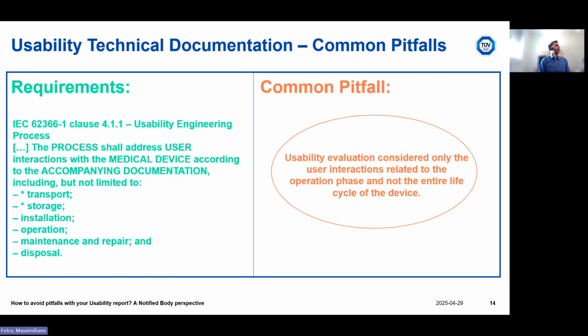Okay, let's start from clause 4.1.1 of standard 62366-1, which requires that the usability evaluation process shall address user interactions with medical devices, including but not limited to transport, storage, installation, operation, maintenance, repair, and disposal. What does it mean? It means that the usability evaluation process shall consider the entire life cycle of the device. Not only the operation phase, so the phase where the device is used on the patient or anyway for treating the patient, but also the other phases where there is a user interacting with the device with a possible impact on the performance and on the safe use of the device.